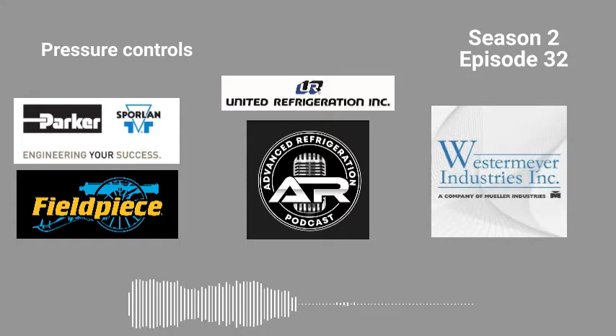Same thing with the high pressure control — high pressure controls take even less time. I just set it to 350 or 400, whatever the spec is or whatever that unit's max pressure is, and see what it trips out at. Same thing with fan cycling controls. The issue is you just need to test them. Do not ever trust the dials on these, especially everything newer in the last two years — the dials don't match anything. I had one the other day where the pressure was set 20 pounds off. I had a pen thermostat that was 11 degrees off right out of the box. So I don't trust any of that anymore. I just go by setting it with nitrogen.